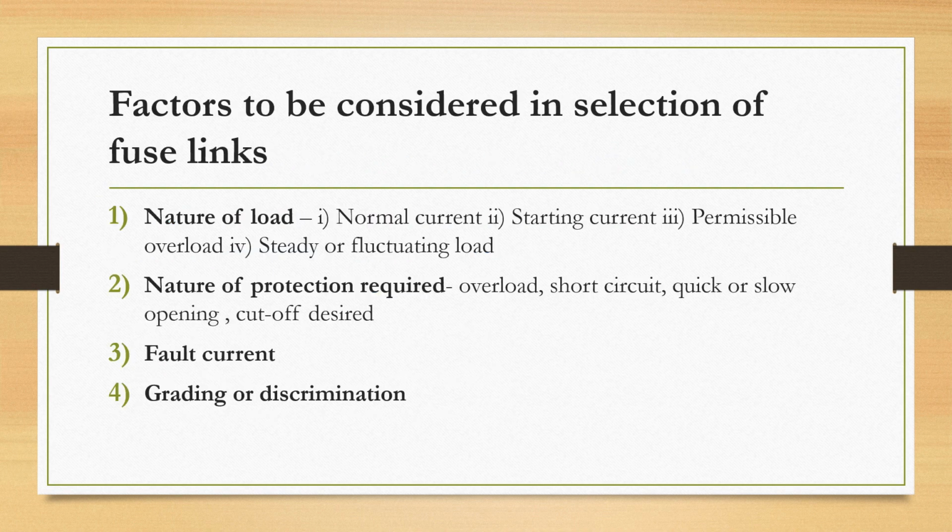Selection of fuse link. The problem is not as simple as you think. An improper blowing out of the fuse itself may create failure of certain systems or stoppage of certain machines. As you are well familiar, at starting, the current is very high. Such conditions should not be treated as abnormal conditions. It's a normal condition. During starting of either DC machines or AC machines, it takes very heavy current for a shorter moment. And surely you won't expect such failures, isn't it?